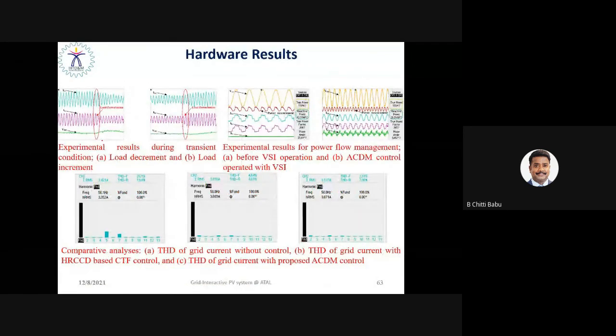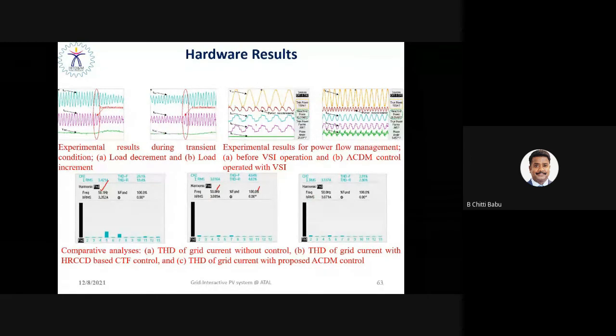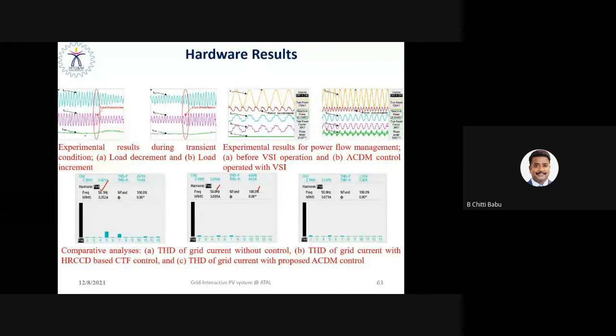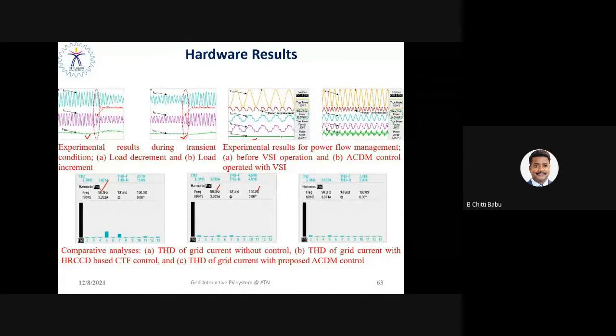Right, for all the cases you can see the harmonic spectrum. The harmonic is the fundamental 50 Hz only that it is injecting. But see the response for all the cases, how the DC link voltage is maintained constant. Throughout the case, the DC link voltage is maintained constant, and moreover the grid current is in phase with the grid voltage, and the DC link voltage is maintained constant, right?